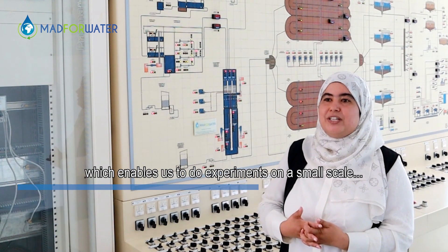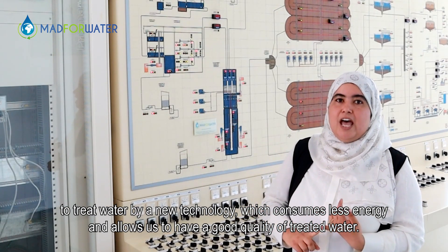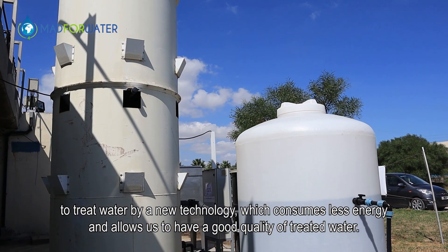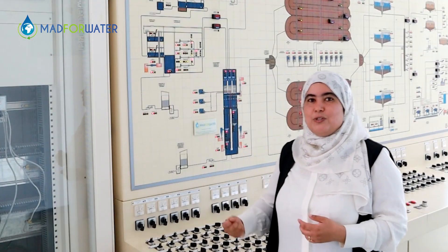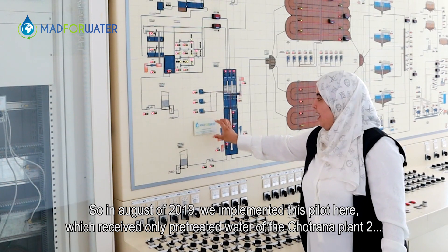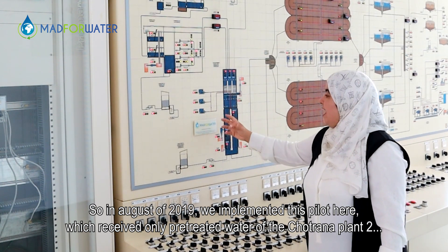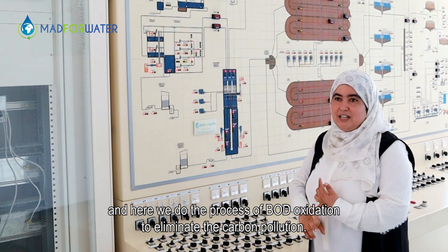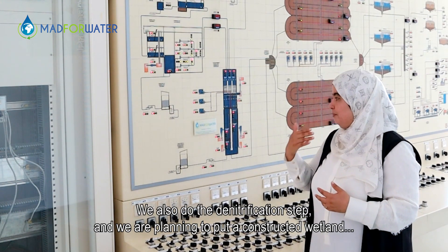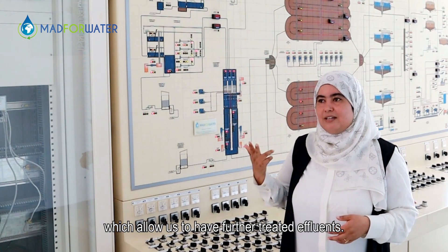We have the chance to work in this MADFORWATER project, which enables us to do an experience at small scale to treat water by a new technology which is a lower consumer of energy and which allows us to have a good quality of treated water. In August of 2019, we implemented this pilot here, which receives the pre-treated water of the plant, and we do here the process — the bio-oxidation to eliminate the carbonic pollution. We also do the denitrification step and we are preparing to install a constructed wetland which allows us to have a finely treated effluent.